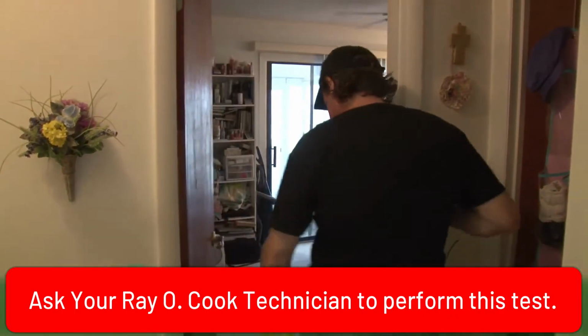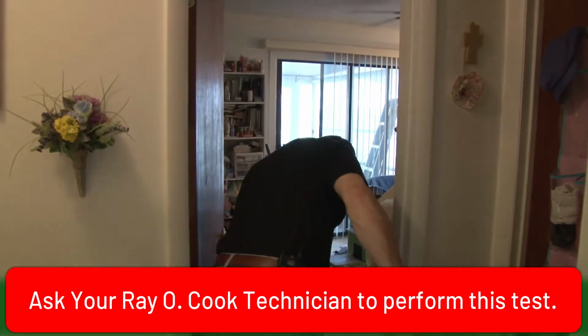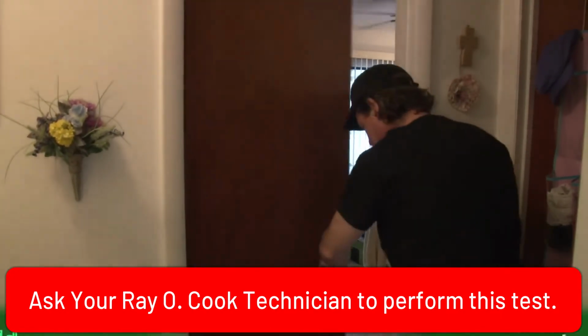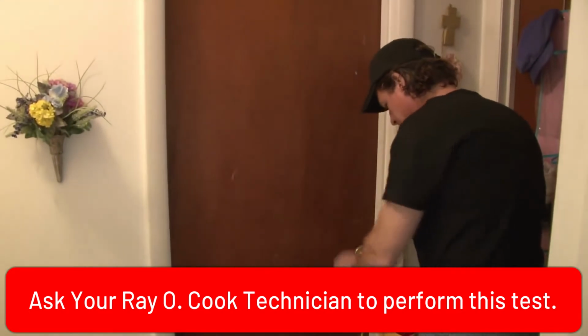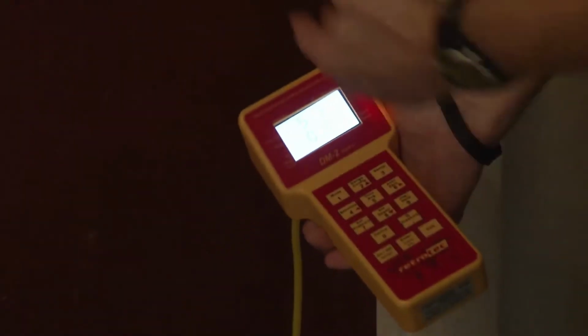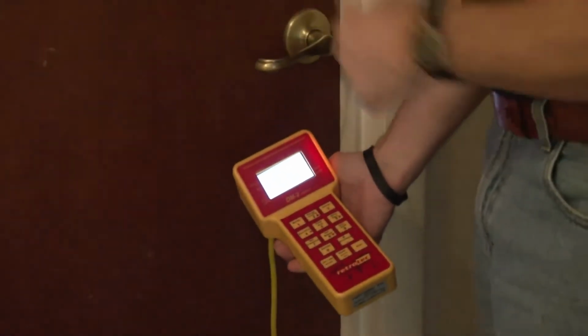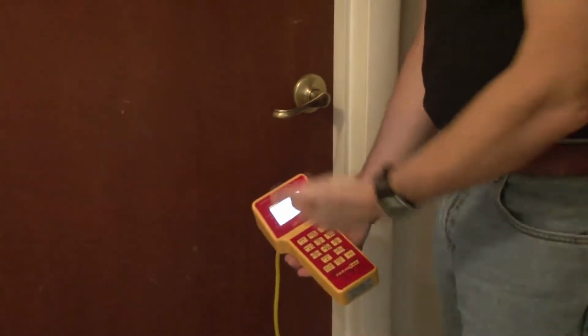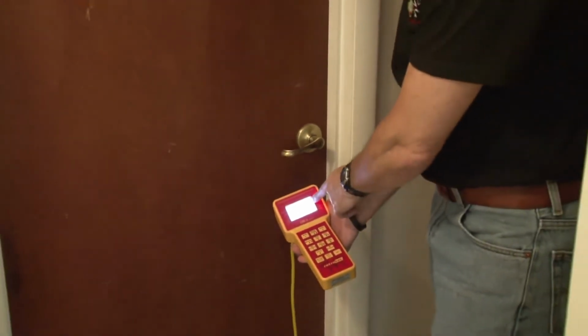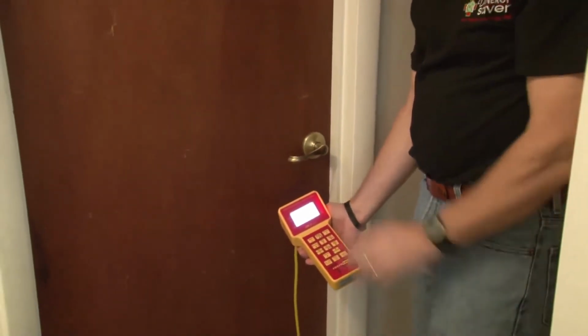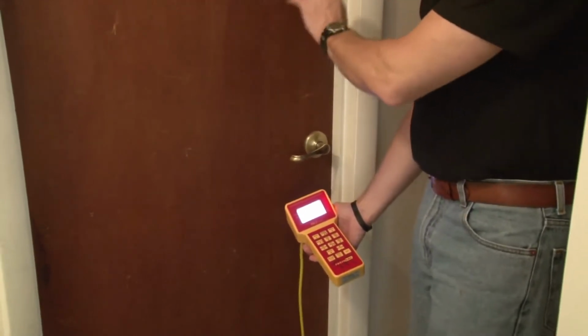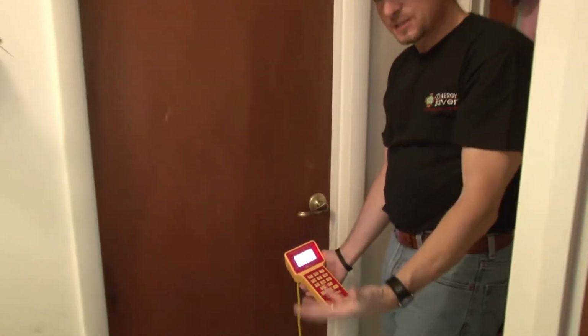Let's measure it. I have a device here that can quantify the pressure difference across the door. And if I close this door, I have 5.4 pascals of negative pressure. 2.5 pascals is acceptable. We have the air handler running. The supply duct is pumping air into this bedroom, but no return air is coming out because the door is closed. 5.3 pascals of negative pressure. That means that side has more pressure, this side has less pressure.